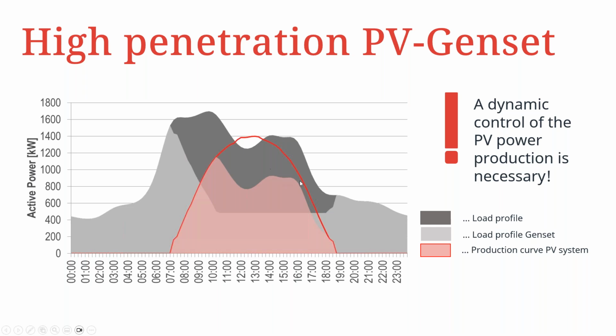And then, like we can see from this PV curve, this red line basically represents the PV generation curve. This dark gray region represents the impact of the PV on the system. Then this light gray represents the power drawn from the genset. So basically, the genset is relieved of its load by the percentage, or by the region, that is colored by the dark gray region. Good.